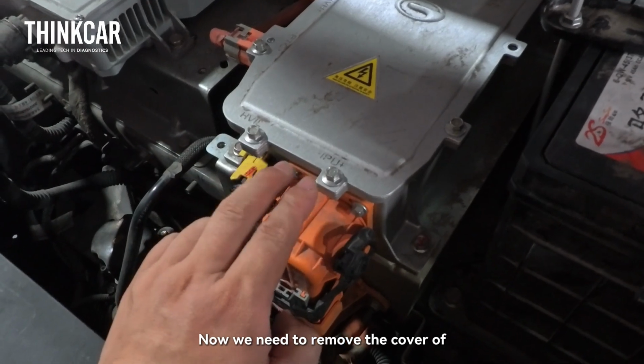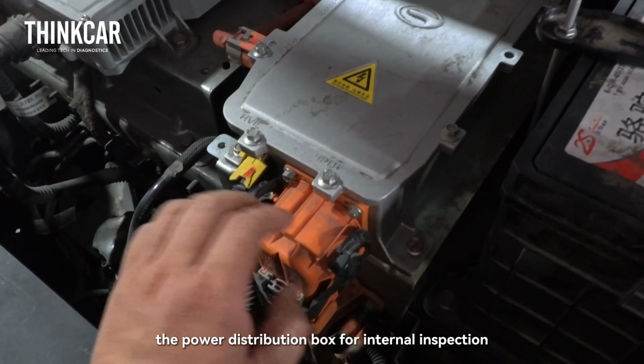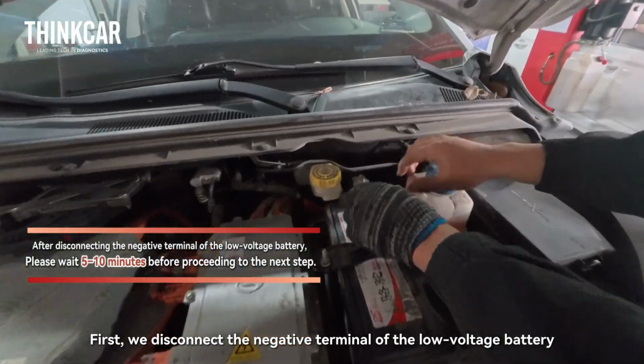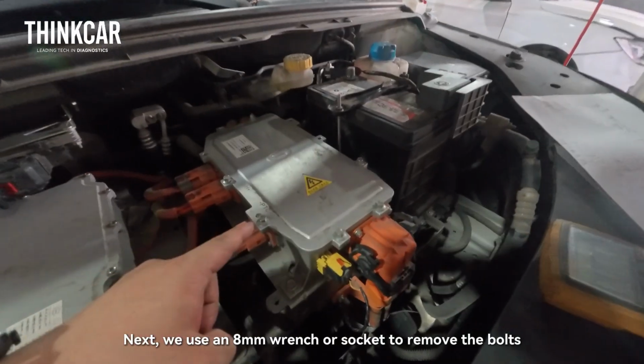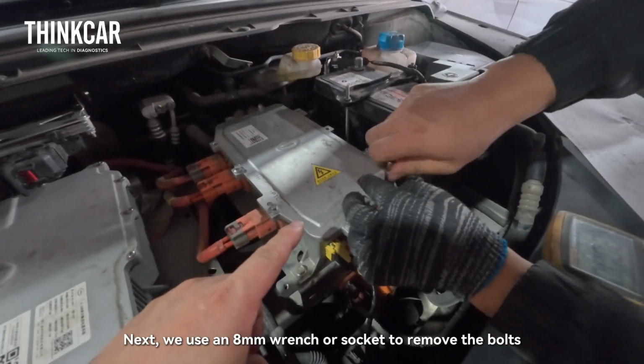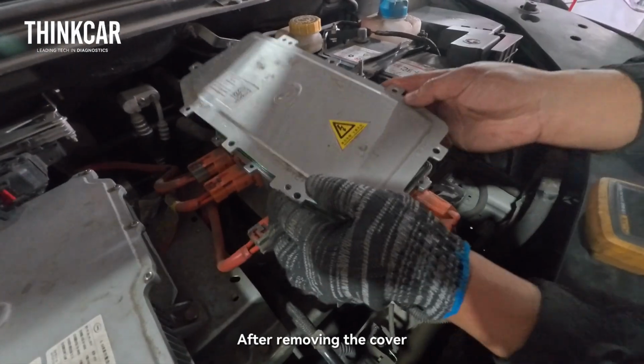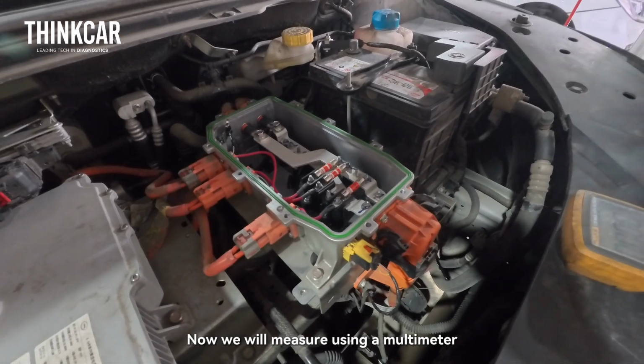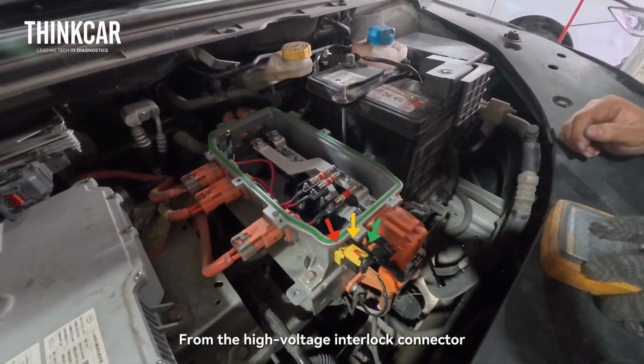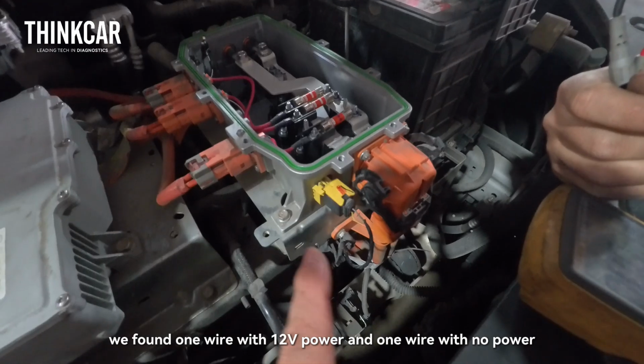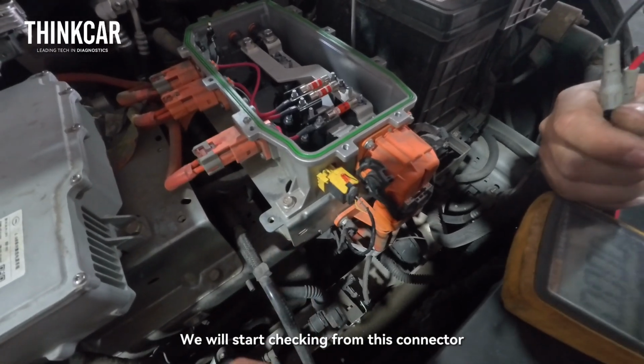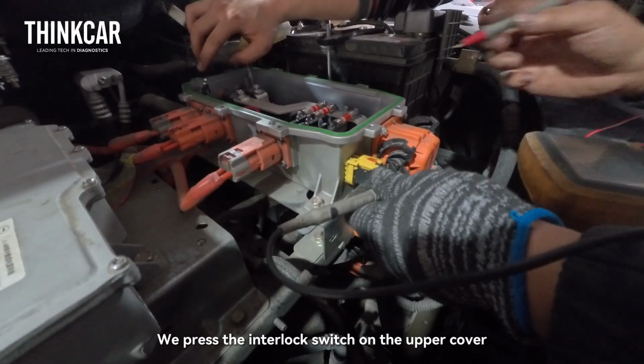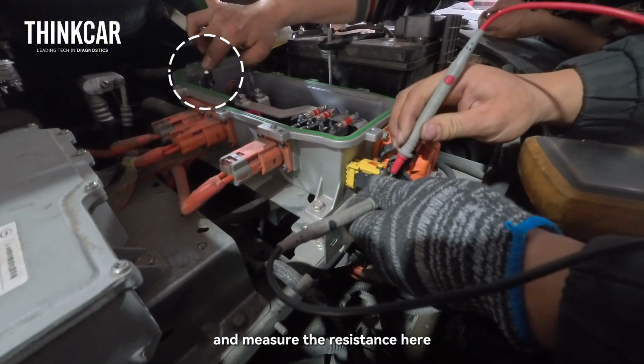Now we need to remove the cover of the power distribution box for internal inspection. First, we disconnect the negative terminal of the low voltage battery. Next, we use an 8mm wrench or socket to remove the bolts. After removing the cover, now we will measure using a multimeter. From the high voltage interlock connector, we found one wire with 12 V power and one wire with no power. We will start checking from this connector. We press the interlock switch on the upper cover and measure the resistance here. After measurement, we find the circuit is open.